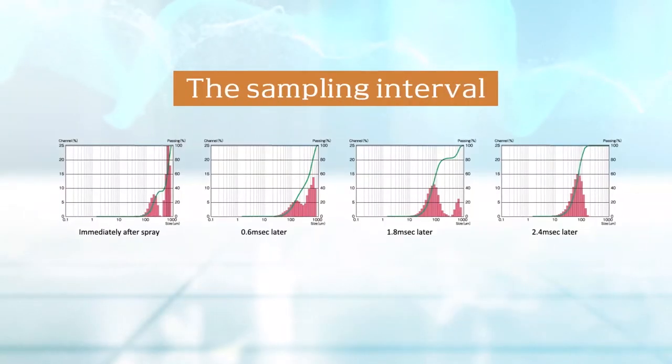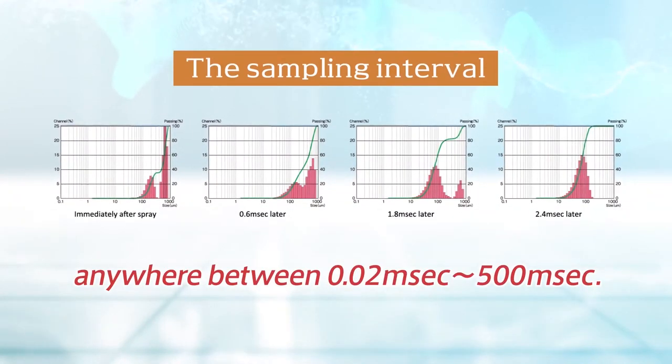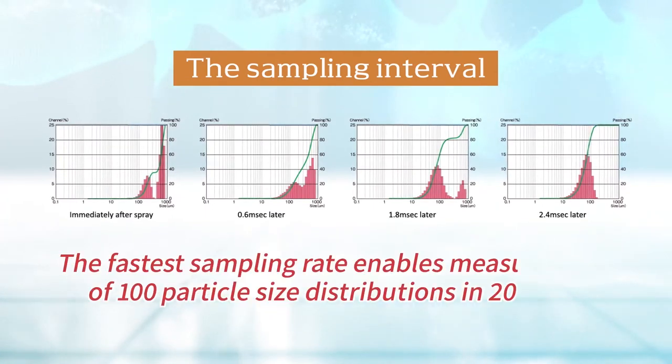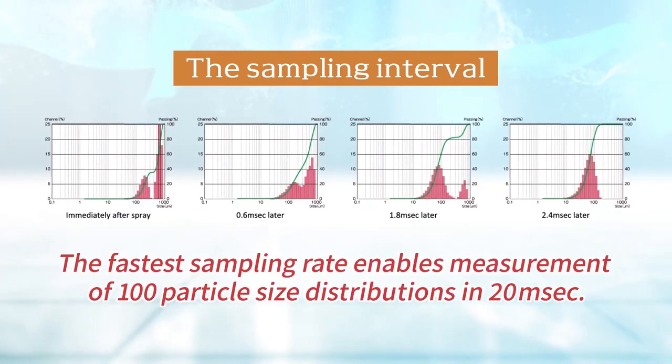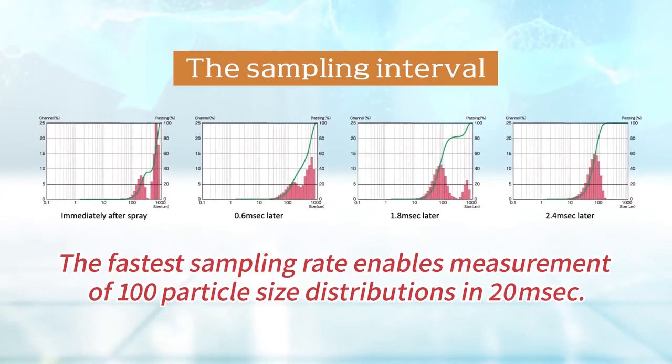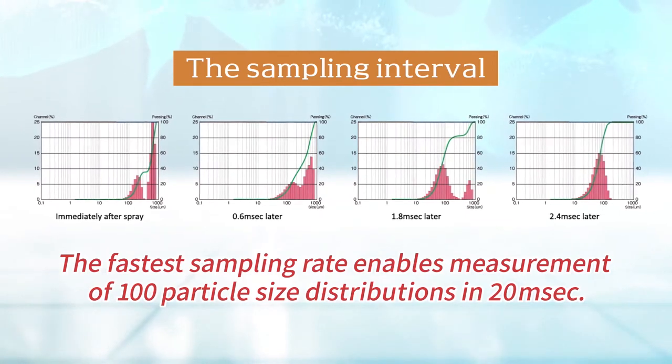The sampling interval for the scattered light can be set anywhere between 0.02 milliseconds to 500 milliseconds. The fastest sampling rate enables measurement of 100 particle size distributions in 20 milliseconds. As a result, changes to droplet particle size can be detected in a short period of time.